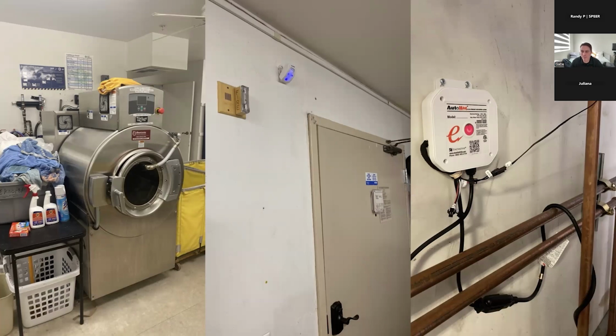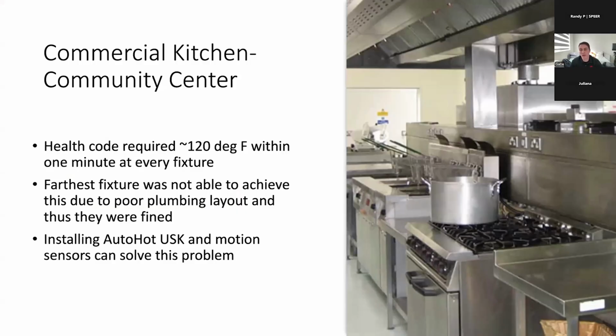So this is just an example of a light commercial application that you could consider. And then we also see other applications where a lot of commercial kitchens, in order to meet health code, have to get hot water at certain fixtures. They've got to get 120-degree water within a certain period of time. And many commercial kitchens aren't able to achieve that because the design of the system just did not permit hot water to get there as quickly.